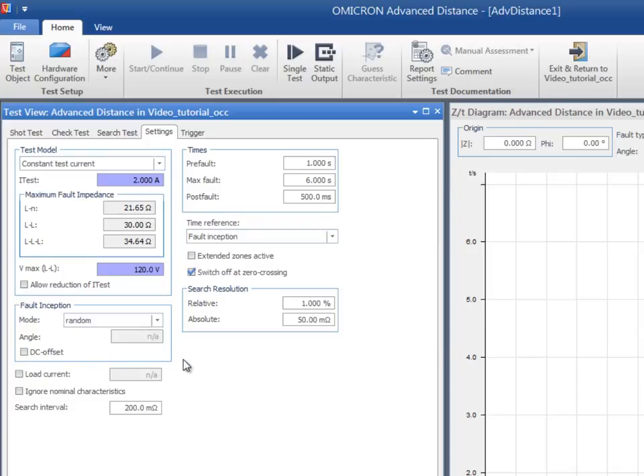The Load Current setting is meant to verify the exceptional behavior of certain relays that react differently if there is current present during pre-fault. As this is unknown for the relay under test, there is no need to activate this option.